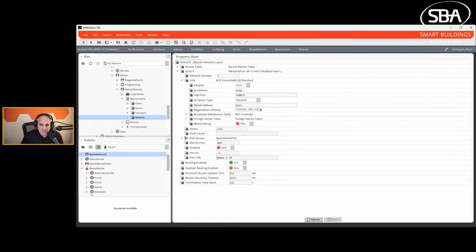All right. So if you recall in my earlier episode, I think it was episode 449, I talked about how BACnet IP's address is its device ID plus its IP address. Now, as I said on Tuesday, if you're listening to this, you need to understand subnets. So it shouldn't be a surprise to you when I say that we're using an IPv4 address. We have to understand our IP address.